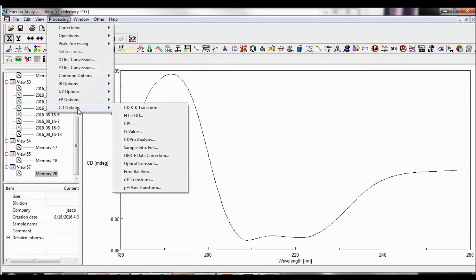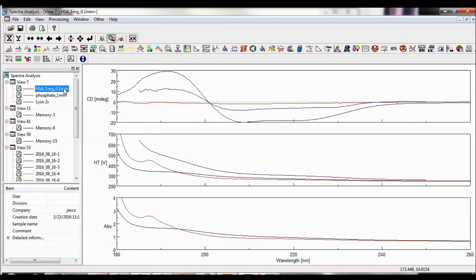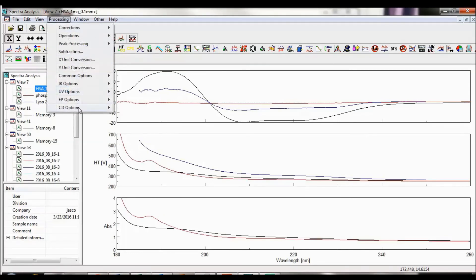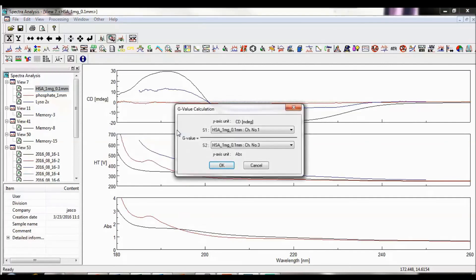There are more CD data processing functions under the CD drop-down list in the Processing tab. CD KK Transform converts the CD spectrum to an ORD or Optical Rotatory Dispersion spectrum using the Kramers-Kronig relationship. HT to OD converts the HT voltage to an absorbance spectrum. The CD and absorbance data can be used to calculate the G value, but you need to select a spectrum that has both photometric modes acquired. Go back to Processing, CD Options, G Value. The G value is the degree of asymmetry of the absorption band and is defined as delta epsilon divided by epsilon.